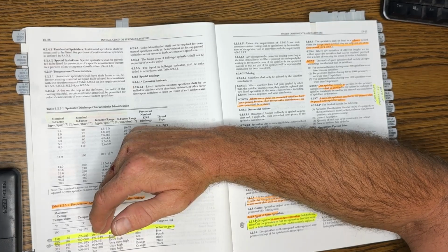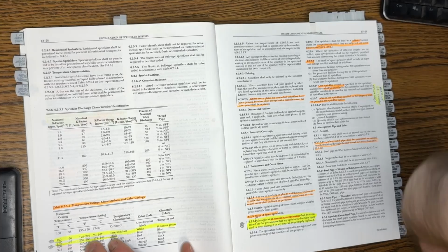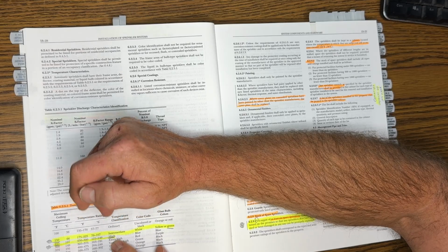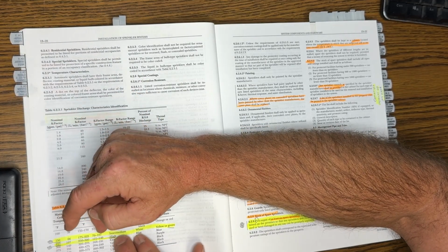And what I mean by that is, let's say you have some heads you're placing next to a roof, a sun, like what can I think? A window in the roof, or next to a heater, that kind of thing. You need to go with ratings that have a higher temperature classification than low. Normally I run 165 degree heads in just about everything I do for typical applications. But if I'm next to a skylight, I'll want to go high. I want to go to 225.